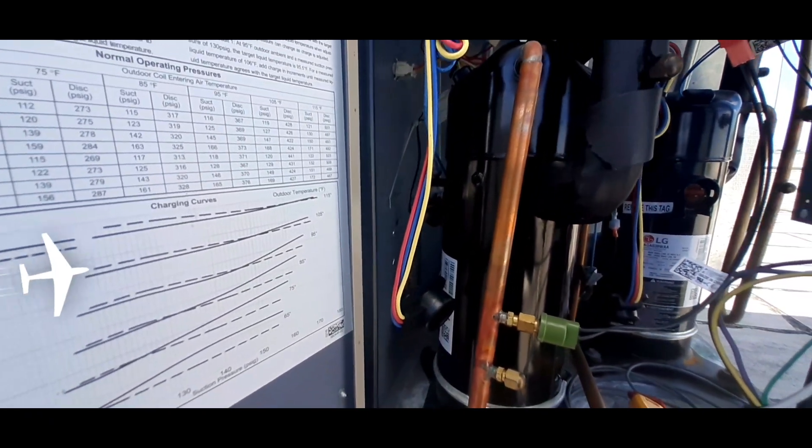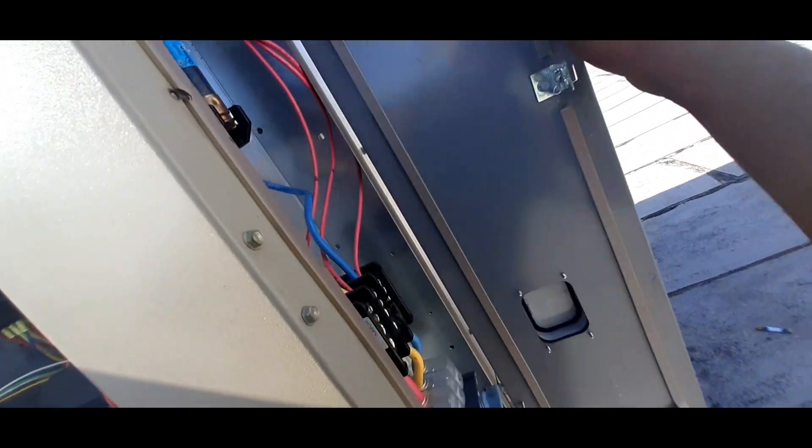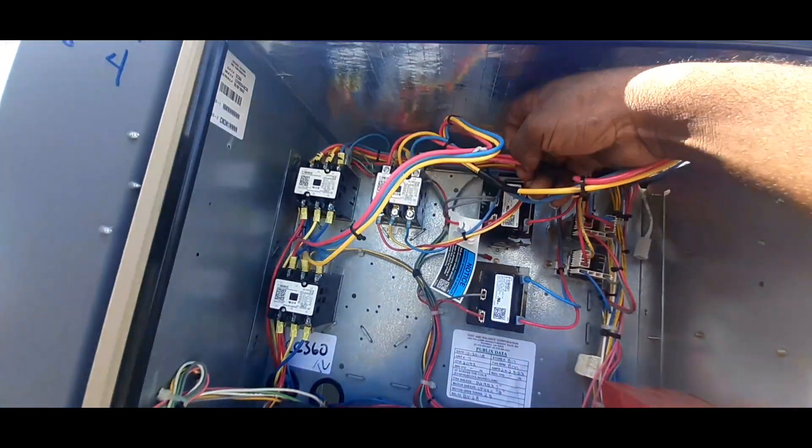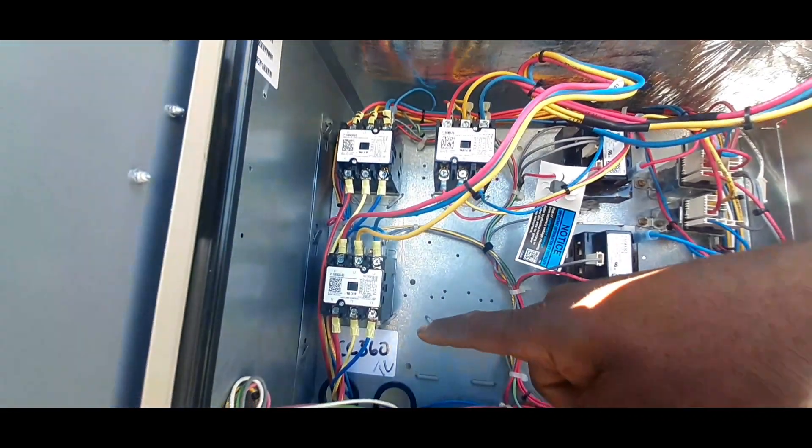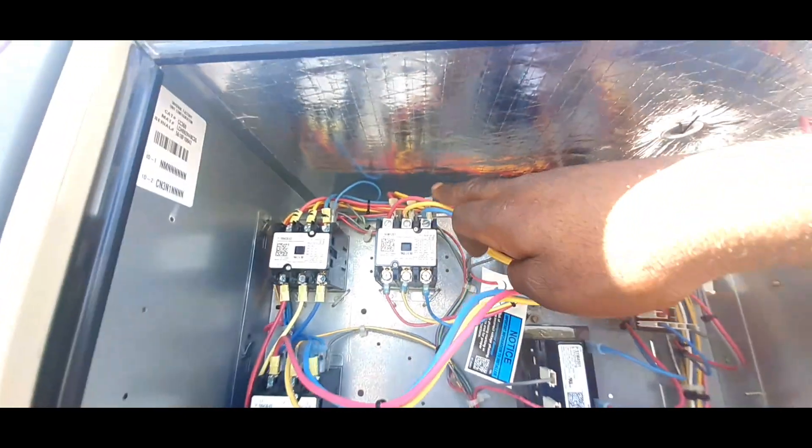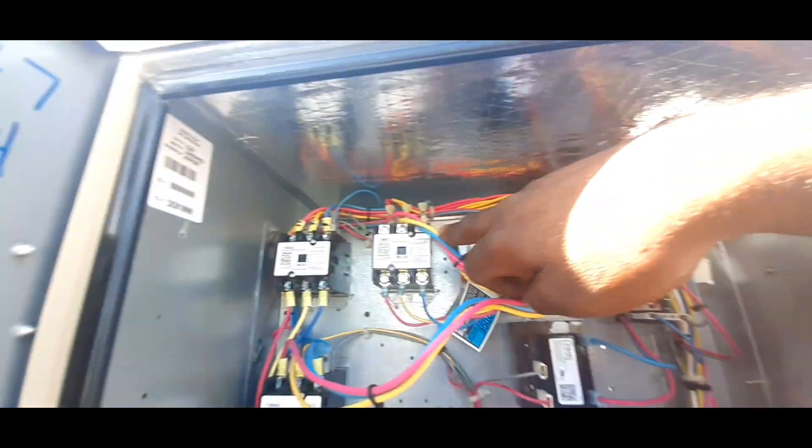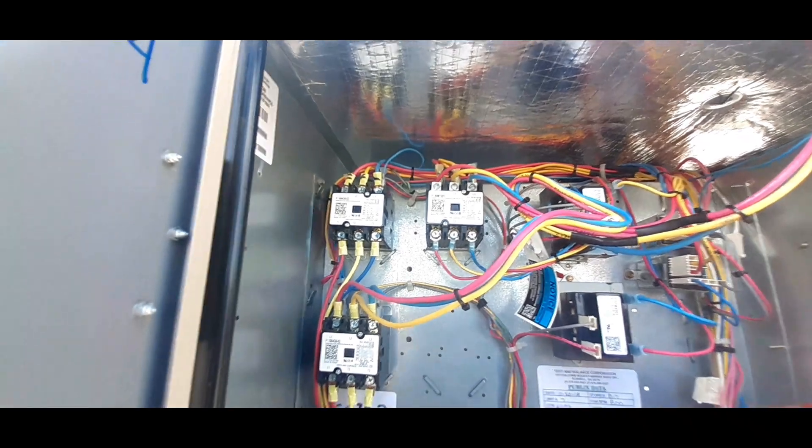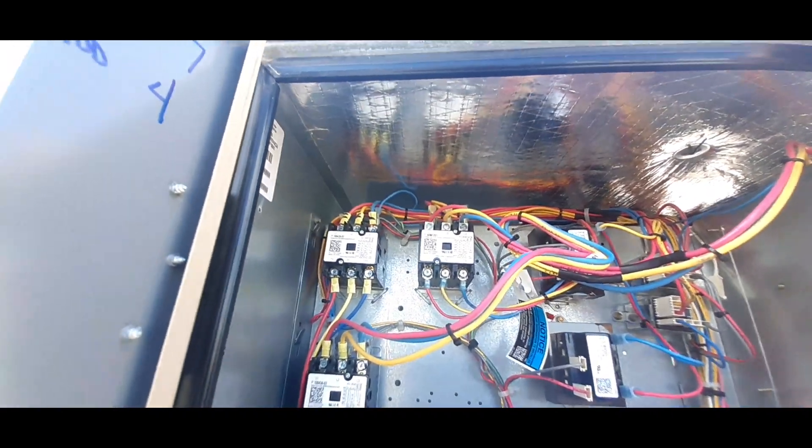So here's my blower contactor, also here's my incoming voltage coming in from the city. As you can see that yellow goes up right up to there, comes around, and that's here. And if you trace it back, it has split into two wires, one going to my blower contactor and also one going to my compressor contactor. And if I look up here at the blower one, it also feeds something else. Not sure what it is right now, but I have to look in the schematic, dig a little bit into it. Whatever's on that load could be shorting out this wire. So I'm just basically kind of eyeballing without looking at the schematic right now. It's old school troubleshooting even though I'm young.